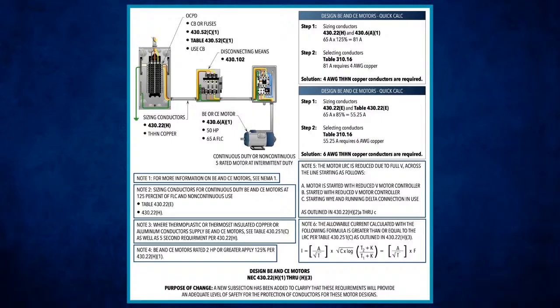Now, I agree. What I like to explain at this point, when I'm dealing with specific conductor applications, you're getting into higher percentages. Now, when you look at that table, you're going to see on that left-hand side your motor control circuit conductors, and then you come across for the application of your article and section, it's going to tell you to look at Article 430, and it's going to say parts 2, 3, 4, 5, 6, and 7.